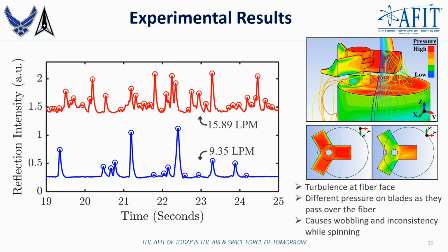So here you can see two examples of the detected flow. Each peak that you see here corresponds to the reflected light. Now, as you can see here, we don't have uniformly spaced peaks, as we would expect if we want to characterize a good flow. So we did a fluid dynamic simulation, and we found that the dynamic at the fiber tip itself is very complex.